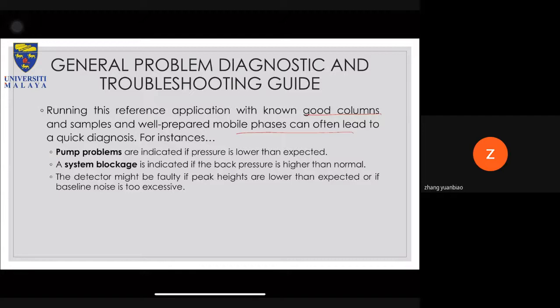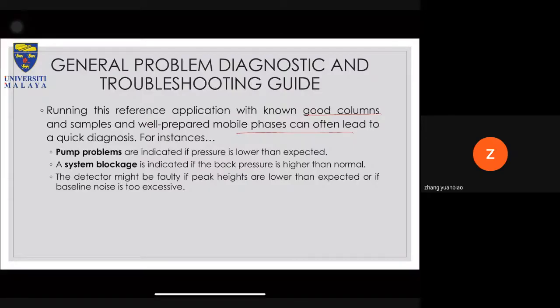So for troubleshooting, normally either you go back to your records, or you look at the system one by one, to try and find what the issue with your system is. Additionally, the detector might be faulty if peak heights are lower than expected or baseline noise is excessive. Faulty here does not mean that it's 100% broken. There might be air bubbles because the degasser system is broken. Okay, so by knowing all this information, you can get an idea of what the issue might be.